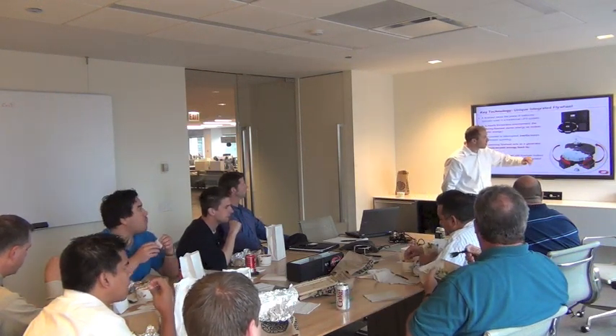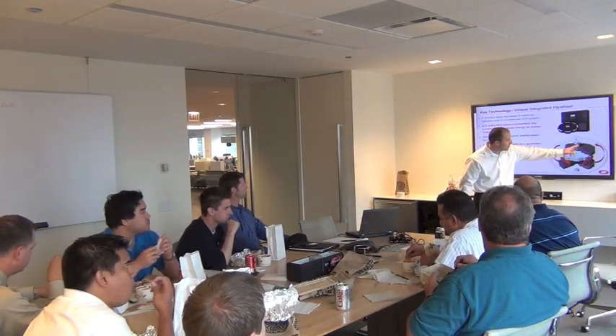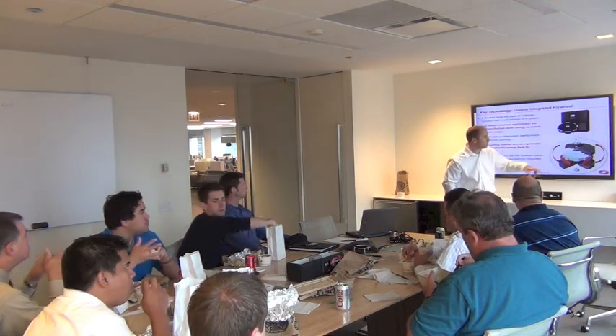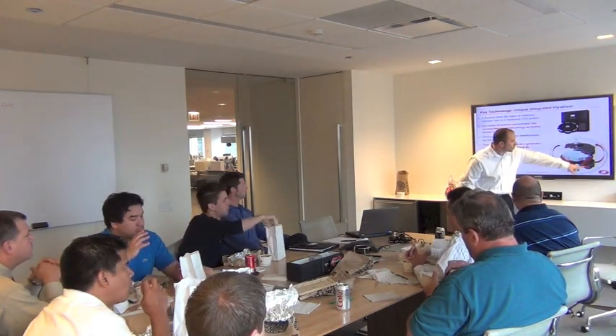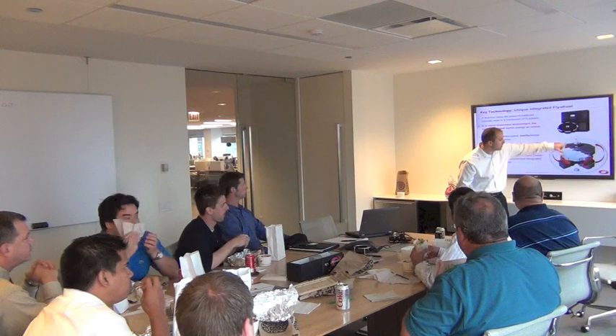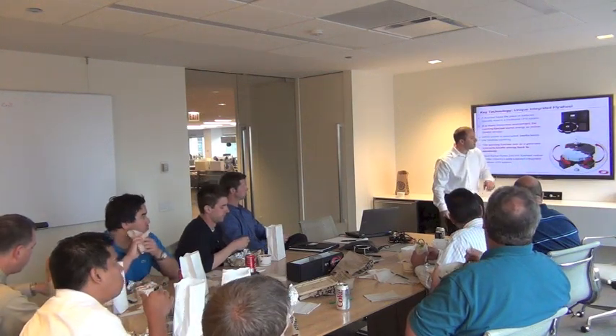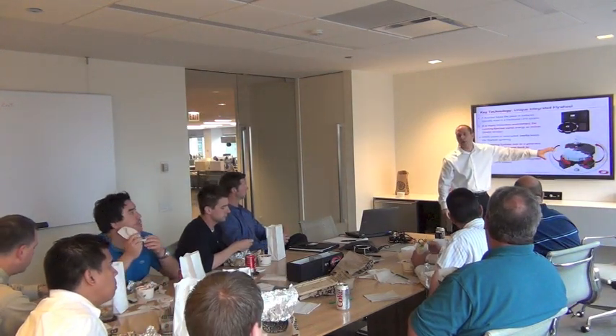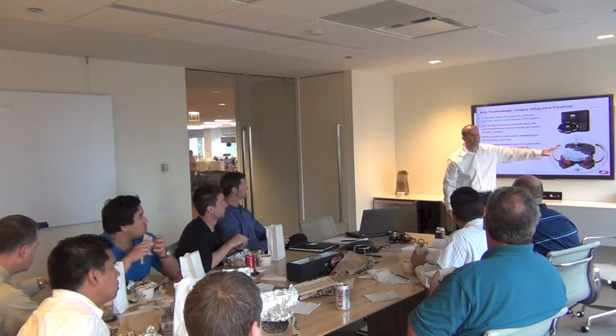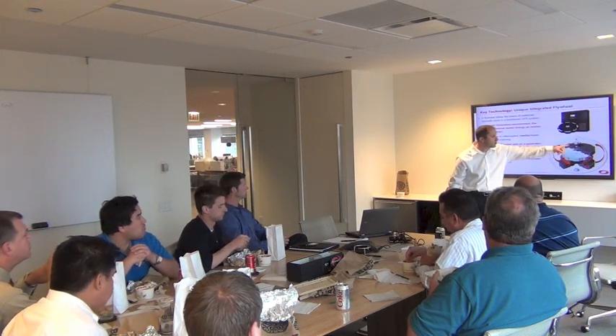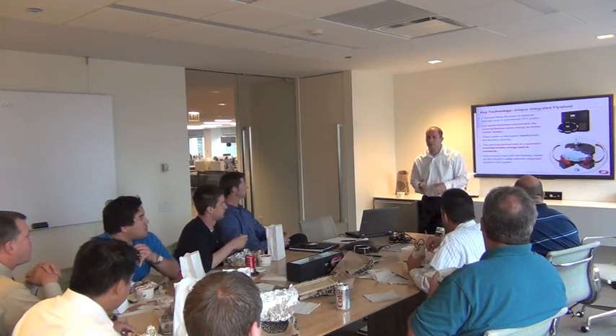Some of the major components of the wheel, basically you have the casting that houses the flywheel assembly. We have an upper and lower field coil, a 3-phase armature, the upper and lower bearings. Basically, there are no wear items on the wheel. It's pretty much a 20 to 25 year wheel. Once every 4 years, you will change the bearings on the wheel, and it's not so much that they wear out.